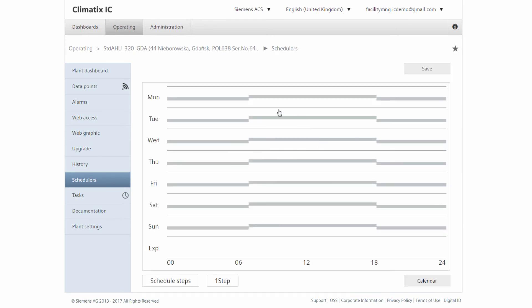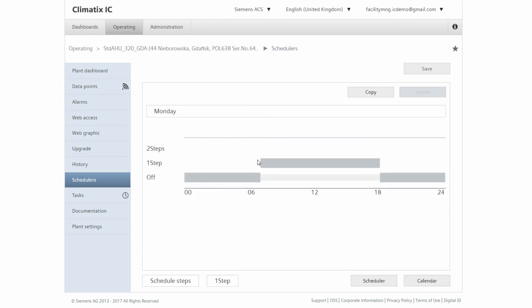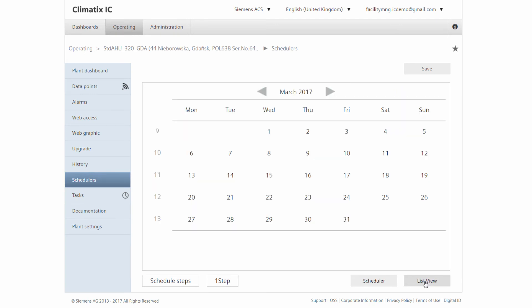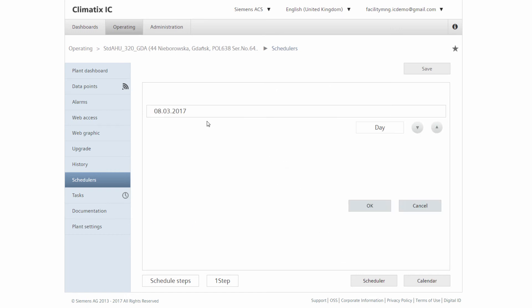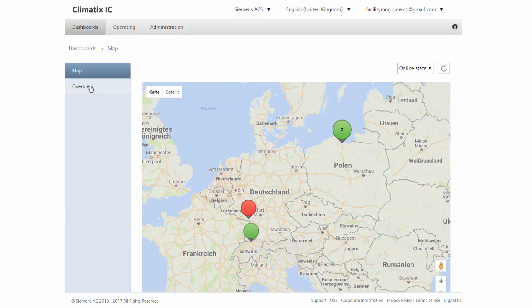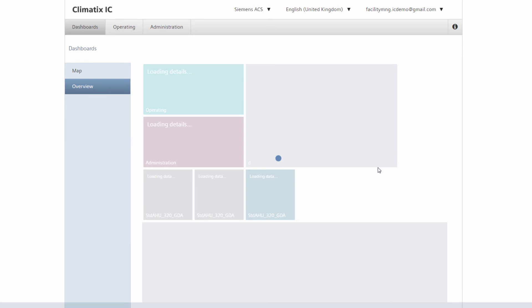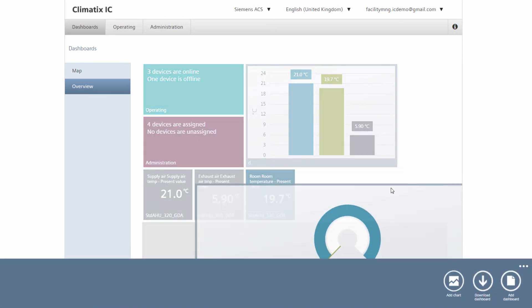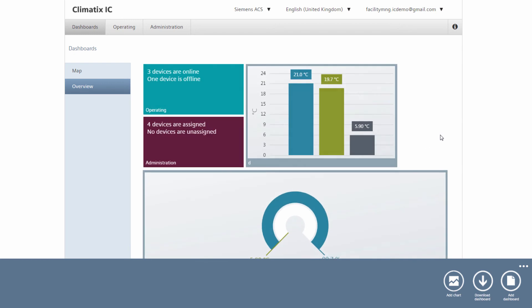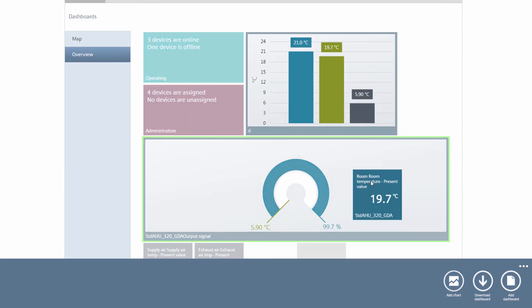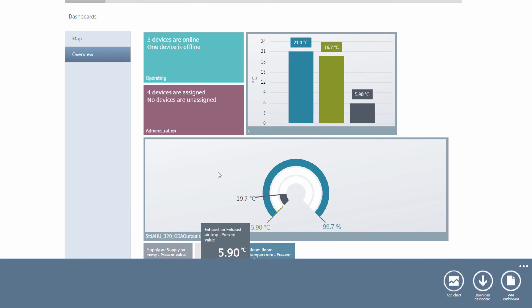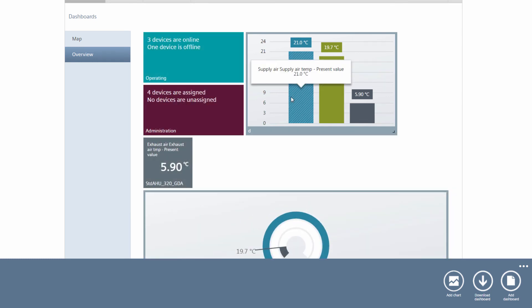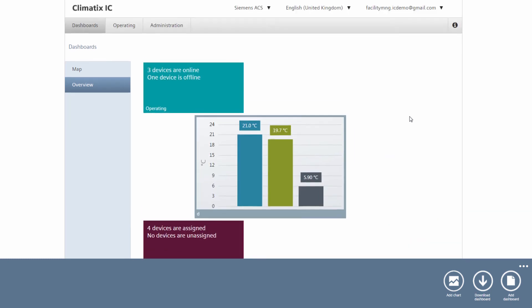Often, system time schedulers are not set correctly and the systems run in continuous operation. As a Facility Manager, we can remotely adjust the schedule and the holiday calendar settings to optimize the energy supply. If needed, we can create personalized dashboards with individual charts and bar charts. We can use the graphics here and simply drag and drop to insert them into the charts. This gives us a personalized dashboard, which we can send to various users for further use.